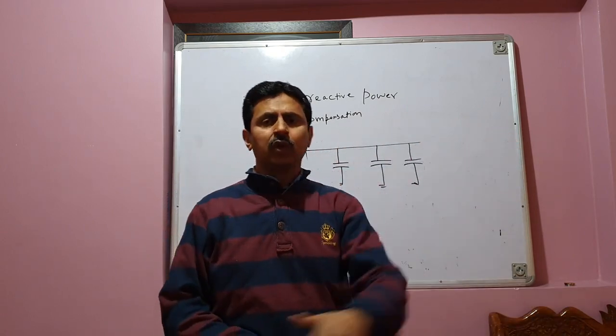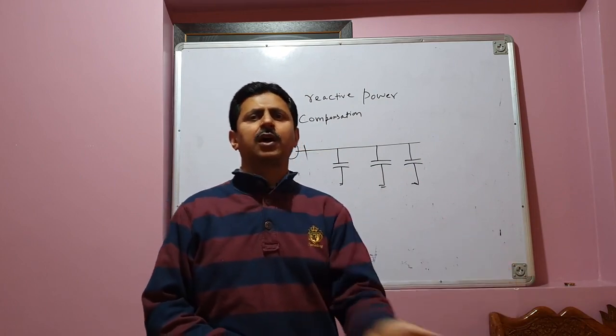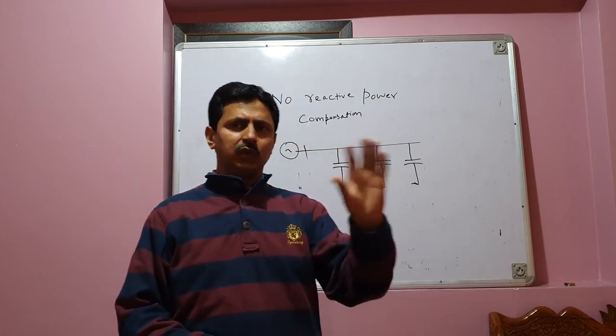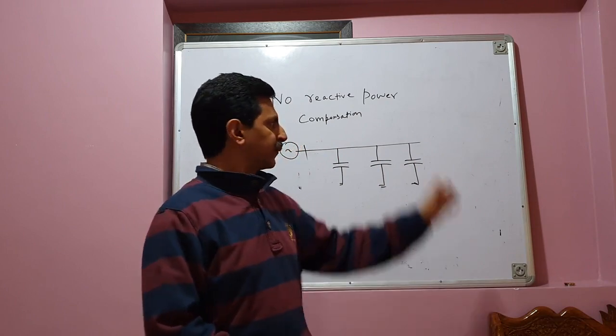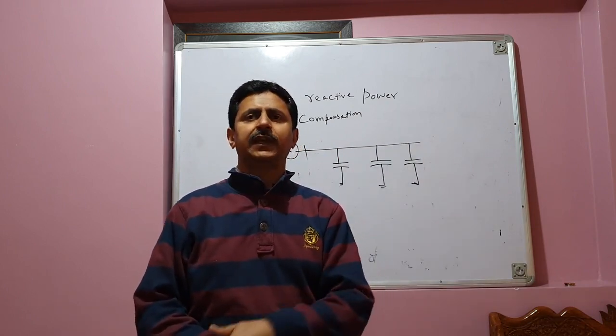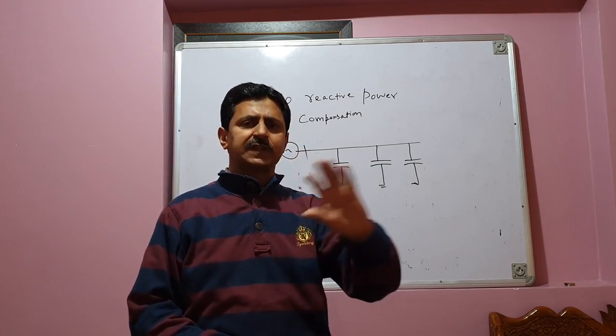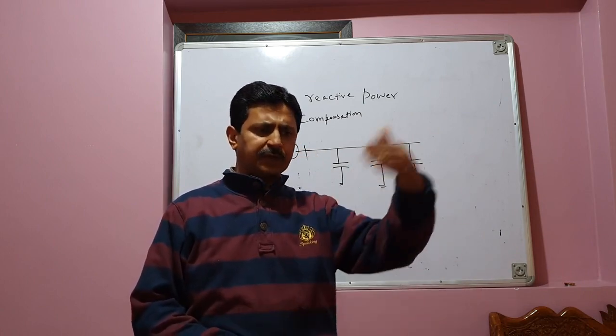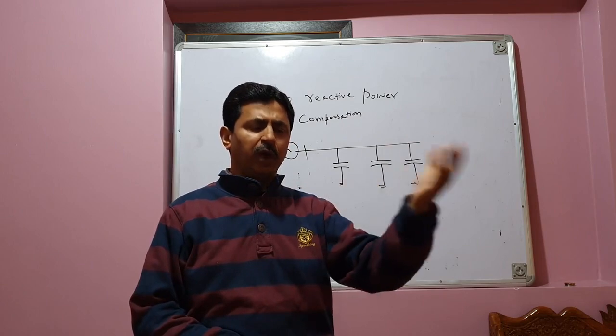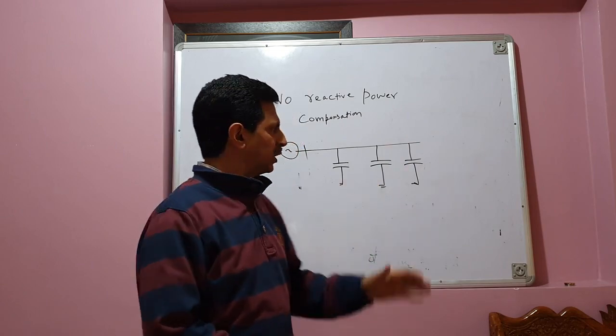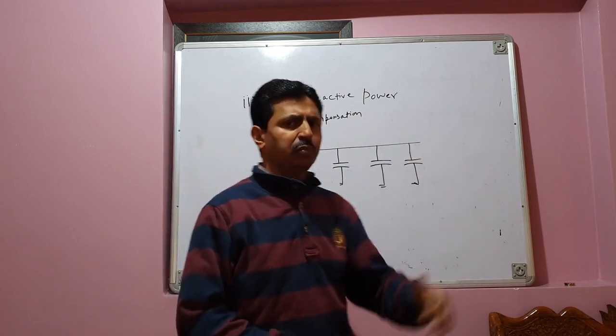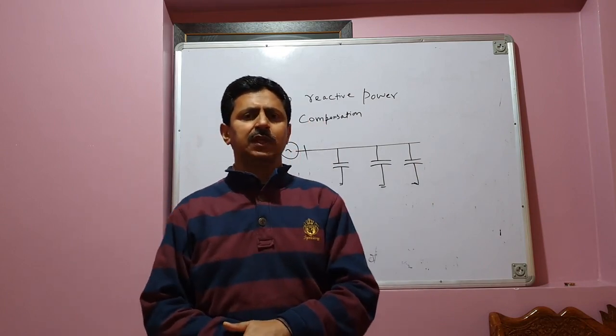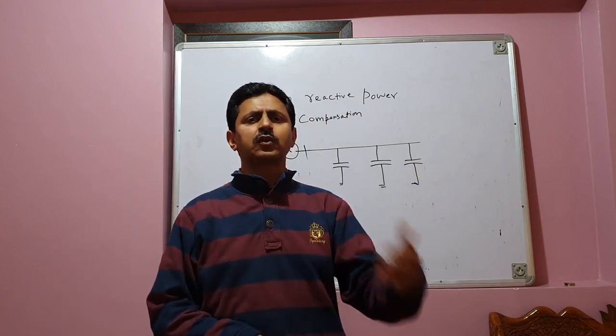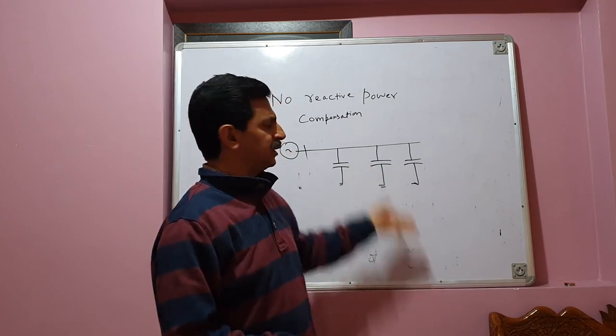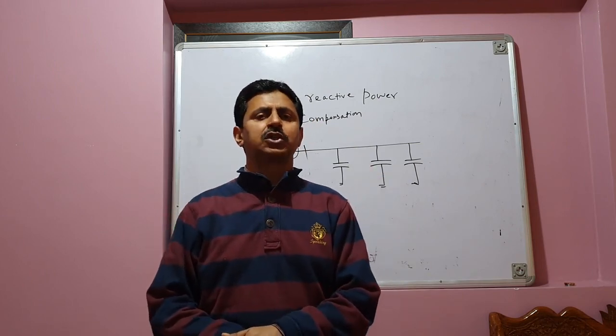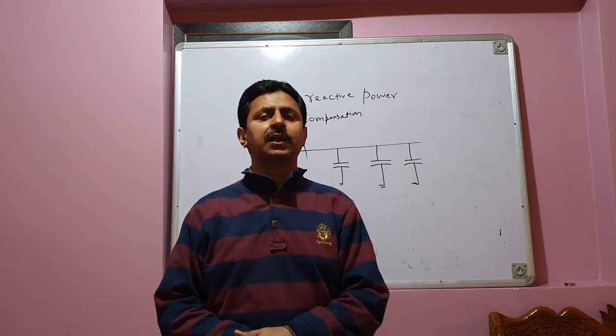which is flowing over the line, which causes large voltage drop over the line, which causes very poor voltage regulation at the other end, that's the load side end, and which makes your system unstable after a certain amount of power flow over it, and which causes power swings, power oscillations in the transmission line. To overcome all those problems, you provide this reactive power compensation through shunt compensators, the simplest being shunt capacitors.